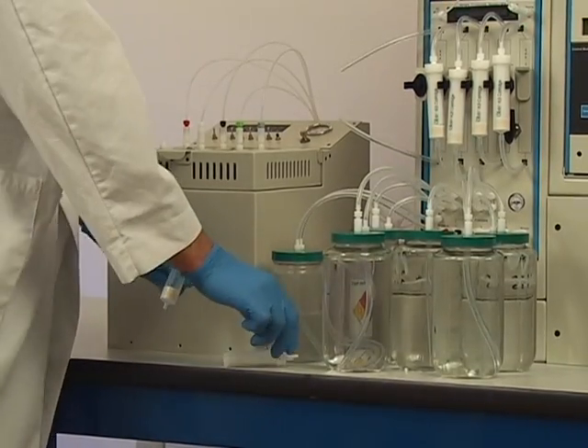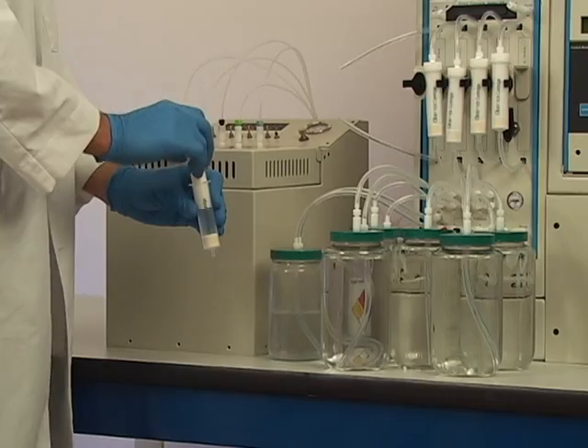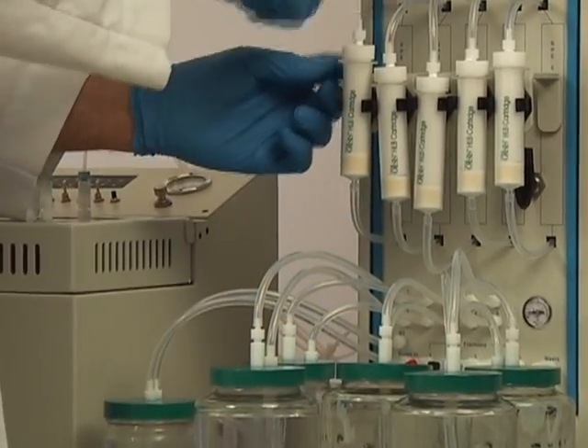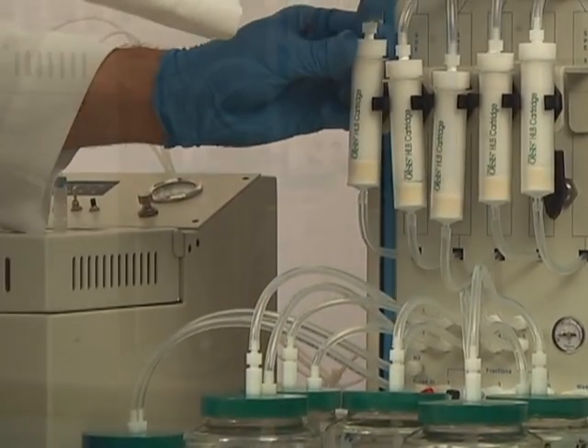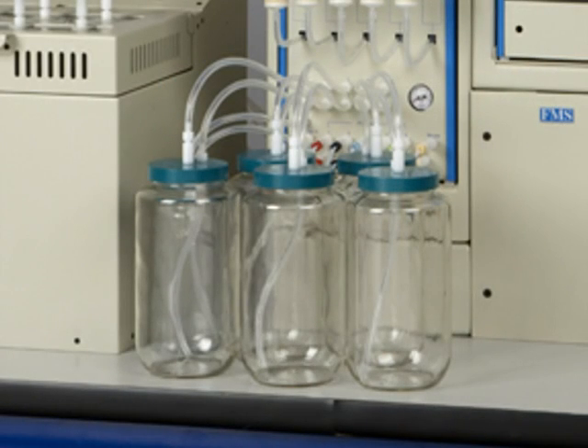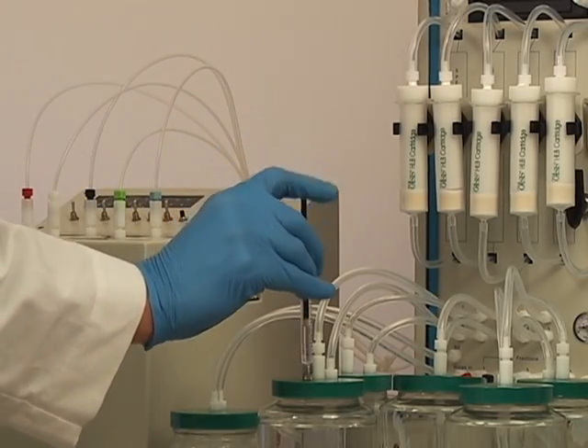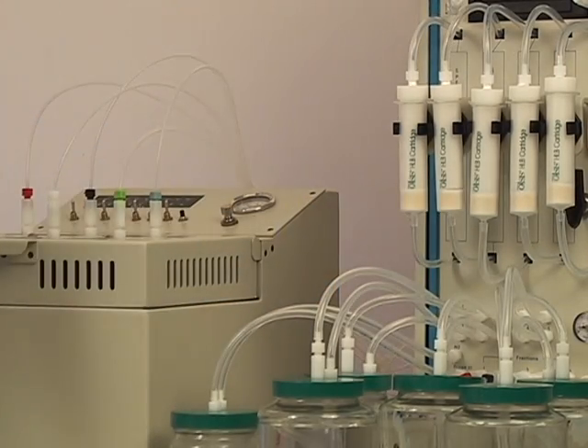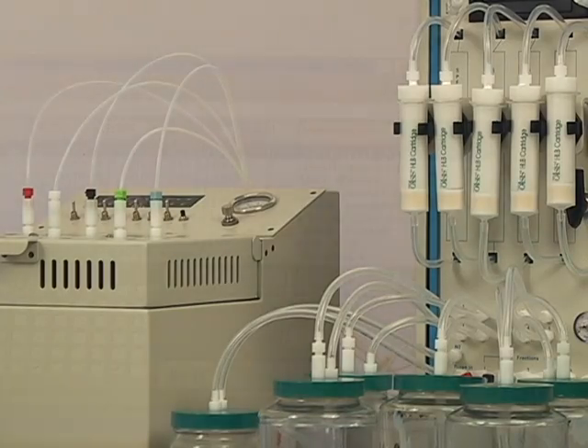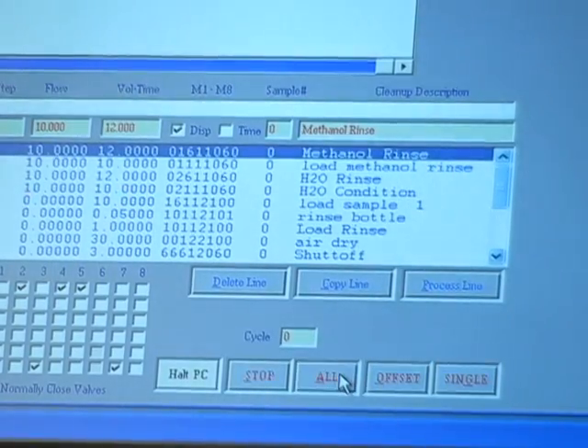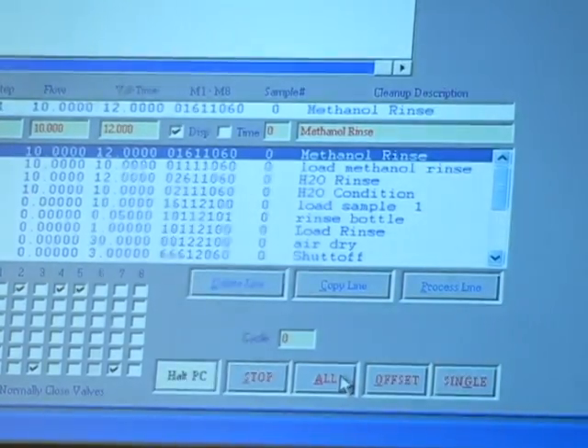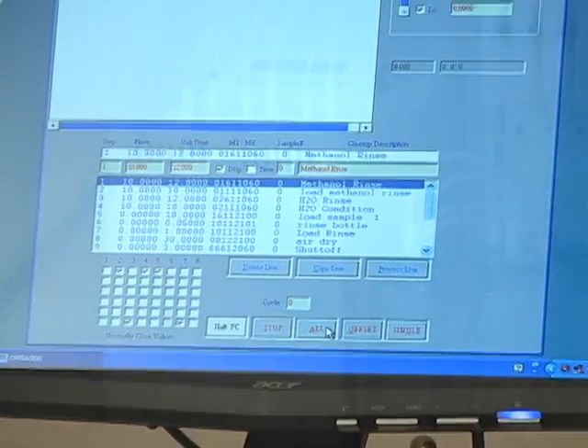Here's how the PowerPrep SPE system works. An SPE cartridge or column is snapped in place with the quick-connect fittings on the unit. A sample to be tested for pharmaceutical byproducts in water from the field in its original collection bottle is attached to the system. The sample is spiked with internal standard. The SPE program is then opened, along with files for concentration, and the program is launched.